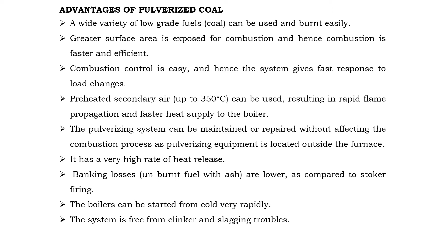The advantages of pulverized coal are: a wide variety of low grade fuels can be burnt easily, and greater surface area is exposed for combustion, hence the combustion takes place faster and more efficiently. Combustion control is easy, and hence the system gives fast response to load changes. Next, preheated secondary air at around 350 degrees Celsius results in rapid flame propagation and faster heat supplied to the boiler. The pulverizing system can be maintained or repaired without affecting the combustion process, as the pulverizing equipment is located outside the furnace.